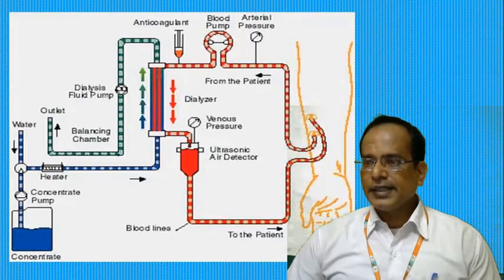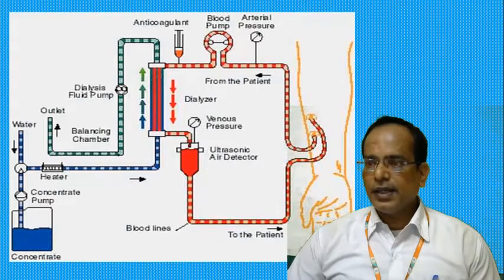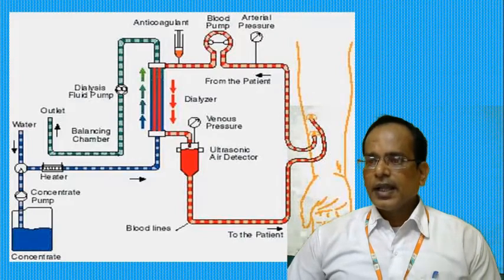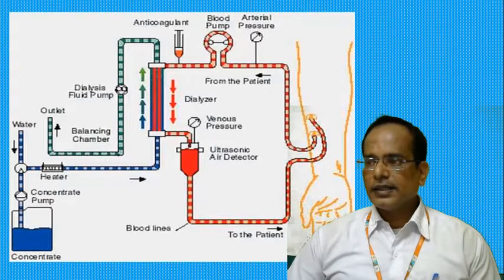So preventive maintenance is even better than educating the user to watch out for the cable, because a hospital might have a very high turnover rate of personnel, requiring a constant in-service education regime. It is also true that Murphy's law and the normal perversity of the universe tend to keep at least 10% of people from getting the word.